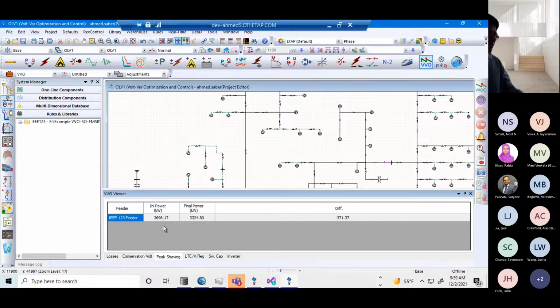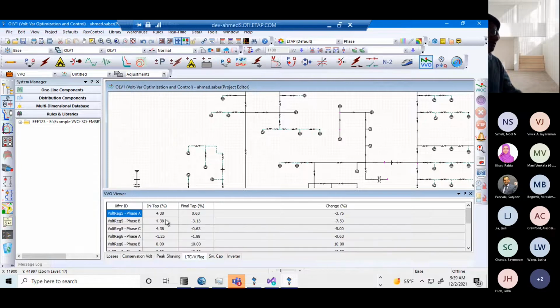So peak shaving, how much do we save? Our initial power was around 3.6 megawatts, but I can get 3.3. So around 371 kilowatts we saved, around 10%. And why? Because we change those taps. Vivek already mentioned we have around 3 or 4 voltage regulators, so we change these voltage regulator settings and get that result.